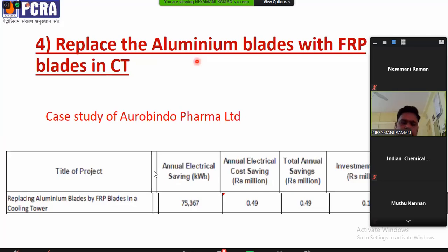We have observed that cooling tower fans are operating with aluminum blades, which are heavier than FRP blades. Because of the heaviness, the load on the motor increases and power consumption will be more. So we suggested replacing them with FRP blades.